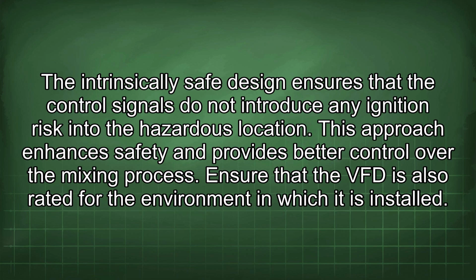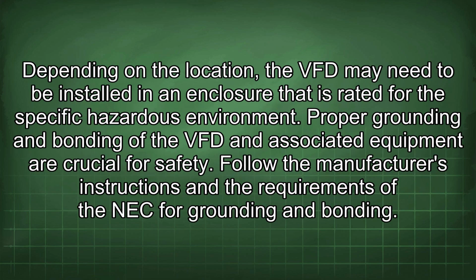Ensure that the VFD is also rated for the environment in which it is installed. Depending on the location, the VFD may need to be installed in an enclosure that is rated for the specific hazardous environment. Proper grounding and bonding of the VFD and associated equipment are crucial for safety. Follow the manufacturer's instructions and the requirements of the NEC for grounding and bonding.